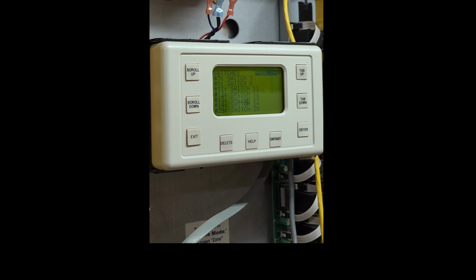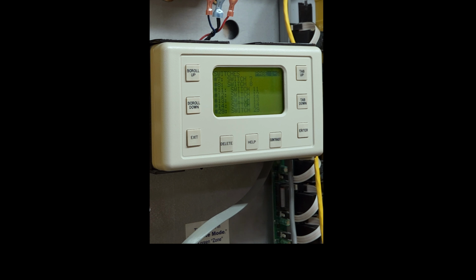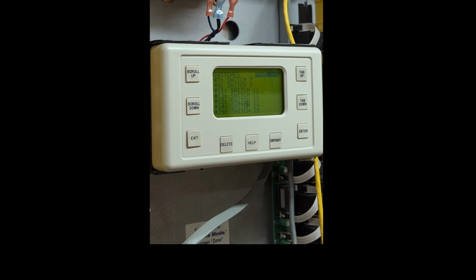29 are missing. Which means there is a place in the line where you have a disconnect. That disconnect doesn't let you see those switches from here, and those switches do not see these panels from there. That's why it's not working. So somewhere you've got a cable disconnected. Okay. But as far as the schedule goes, I can help you with the schedule, but I cannot help with switches that are not being seen until we find out what happened to them.